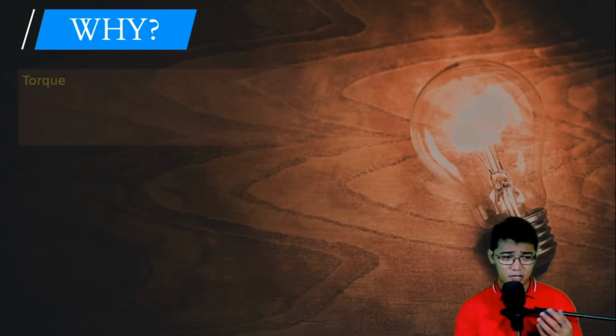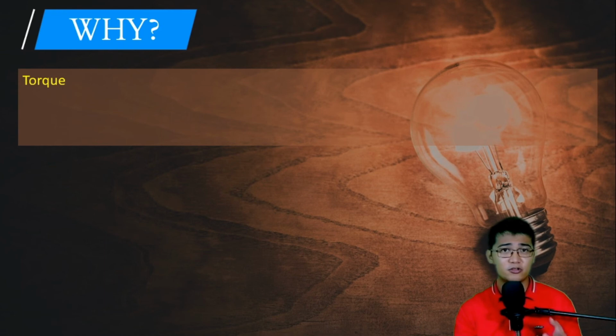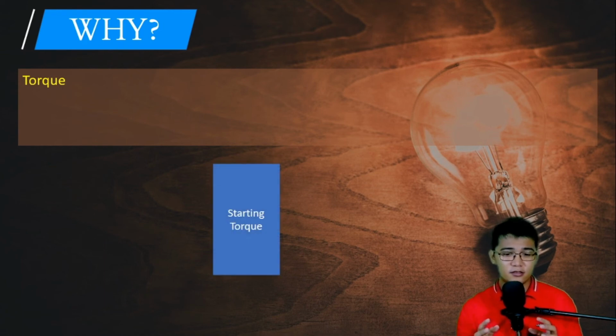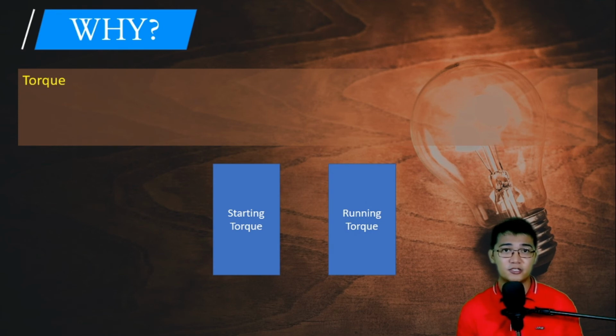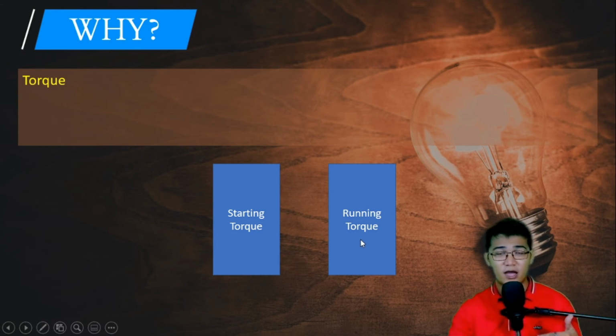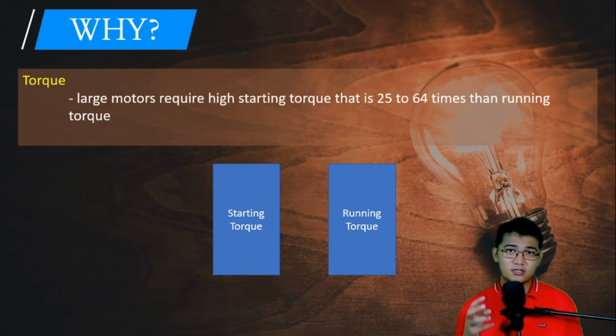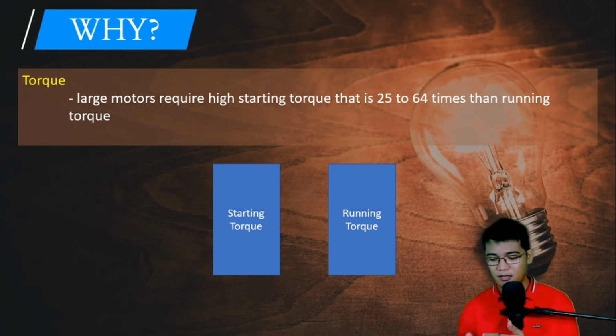Another reason why we employ electric motor starting methodologies is because there are two types of torque related to a motor. Isa is para mapaandar natin ang ating motor, which is known as the starting torque. Ang pangalawa naman is para manatiling umaandar ang ating motor, or the running torque. Typically, the starting torque of large electric motors is actually 25 to 64 times that of the running torque, meaning 25 to 64 times of that will be the torque needed in order to start.